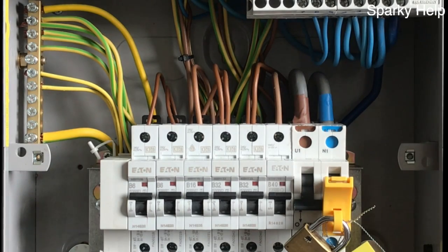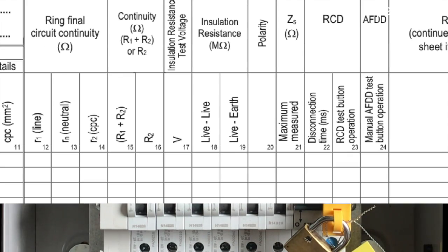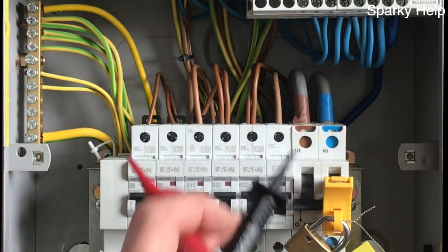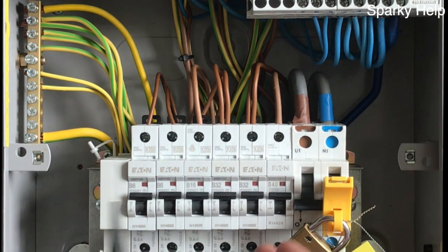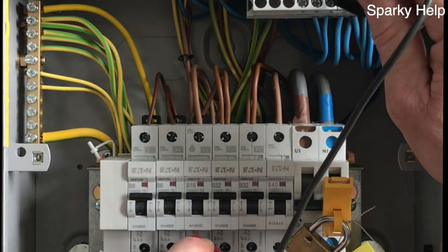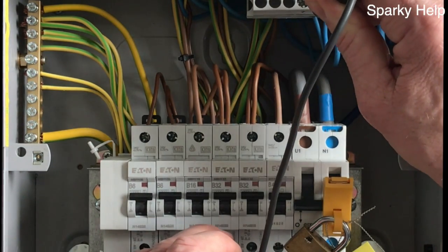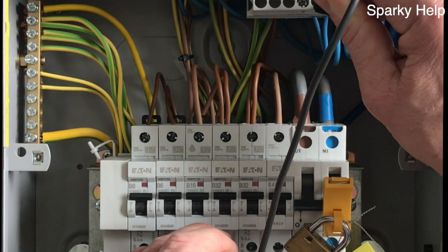So we have two columns to fill in our regs schedule of test results, live to live and live to earth. It doesn't elaborate on what's what. Remember, line and neutral are both live conductors. So with all switches turned on, we can actually go on either side because they're all switched on anyway. And live to live, I'll just go lines to neutrals in place and press the button.